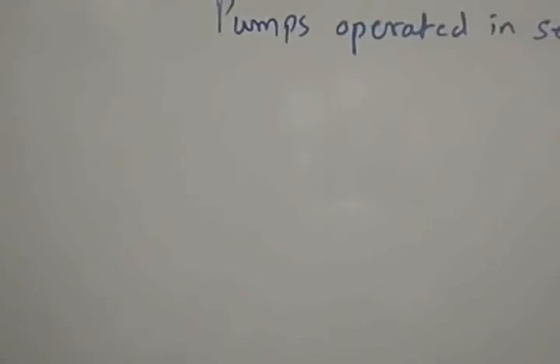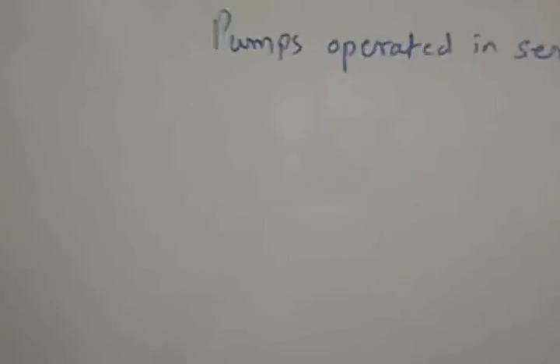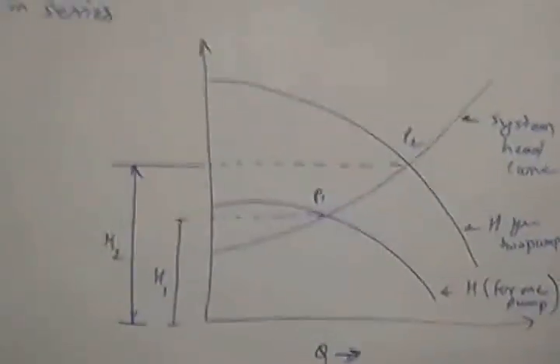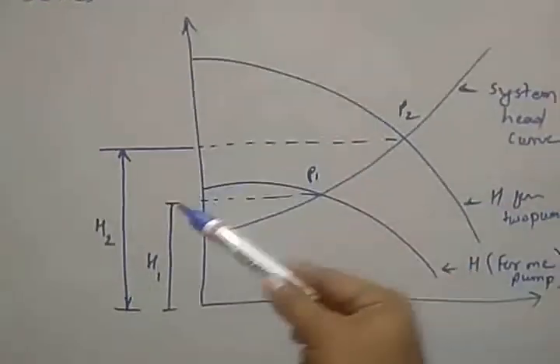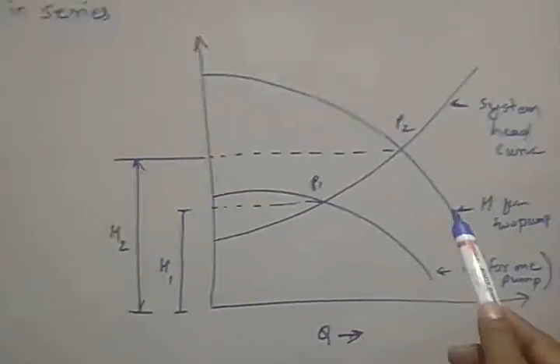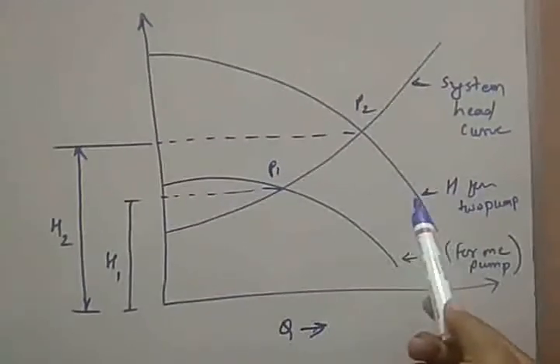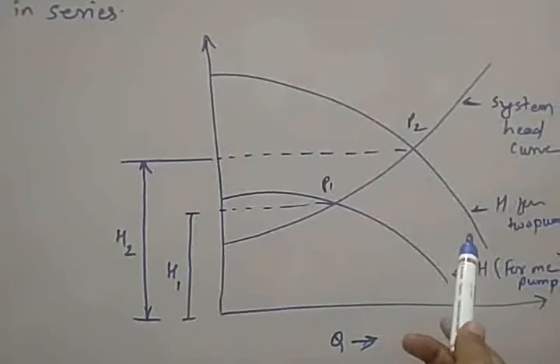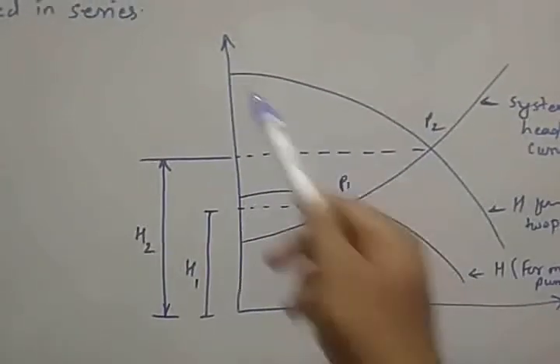Now we will see the operating point or range for pumps in series. In this case, the H versus Q curve for the individual pump is plotted, and also the H versus Q for the total head equal to the sum of heads of individual pumps for the same varied discharges. In the plot, this is the system head curve, this is the H versus Q plot for a single pump, and this is the H versus Q for the sum of heads of two pumps.